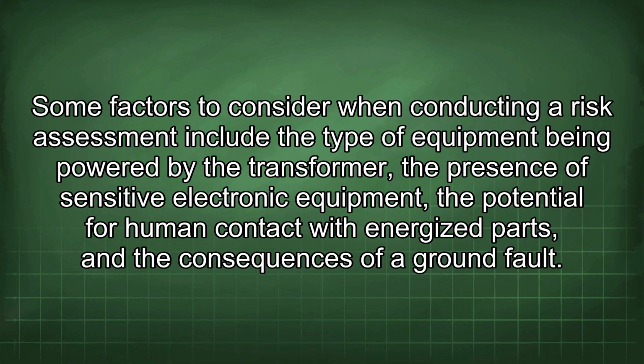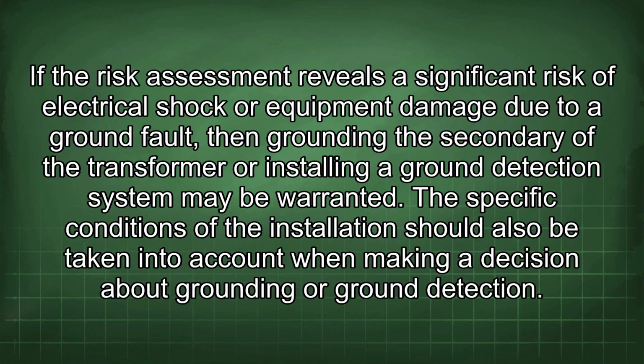Some factors to consider when conducting a risk assessment include the type of equipment being powered by the transformer, the presence of sensitive electronic equipment, the potential for human contact with energized parts, and the consequences of a ground fault. If the risk assessment reveals a significant risk of electrical shock or equipment damage due to a ground fault, then grounding the secondary of the transformer or installing a ground detection system may be warranted.